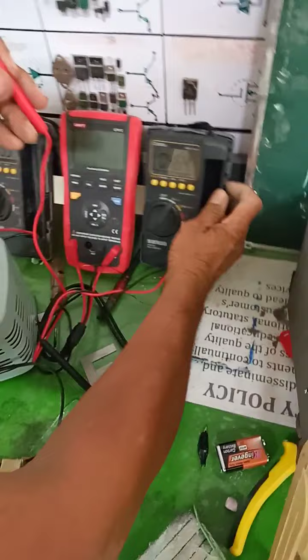The primary is now reversed. We are using 9 volts here, 0, 9. Supposed to be, this is the secondary and this is the primary, but we invert the situation. The primary winding here, which is 0, 9, is supplied with 9 volts from this variac transformer. We reduce the voltage from 220 volts from the outlet distributed by the utility company to 9 volts by using this variac transformer. Actually, there is an induced voltage at the secondary, 224 volts. Meaning to say, it is a step-up transformer, because the primary is 9 volts but the secondary now is 225 volts. So there is an induction at the secondary.